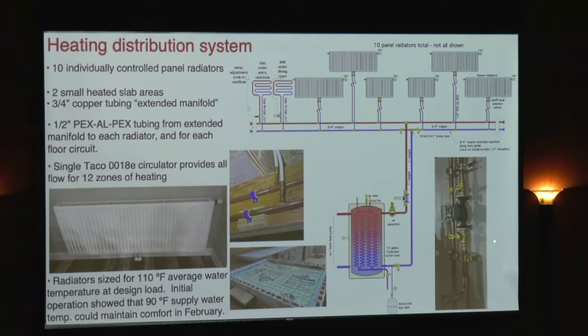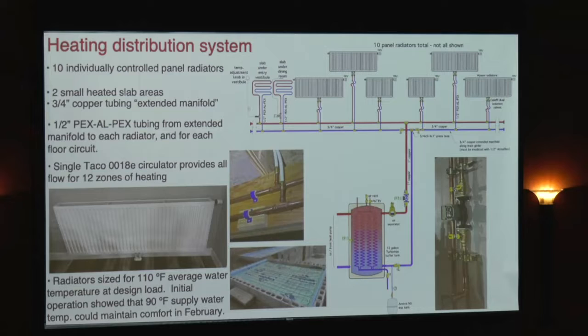And there's the circulator. Again, that's pumping this entire distribution system. And this pump will vary its speed as these thermostatic radiator valves open and close. So as valves start to close, the pump will sense an attempt to go to higher differential pressure, and then the electronics in the pump will reduce the speed of the motor and bring the differential pressure back down again. So I call it cruise control for differential pressure. And again, that's a built-in algorithm, and pretty much all the major pump suppliers in North America have these products now.